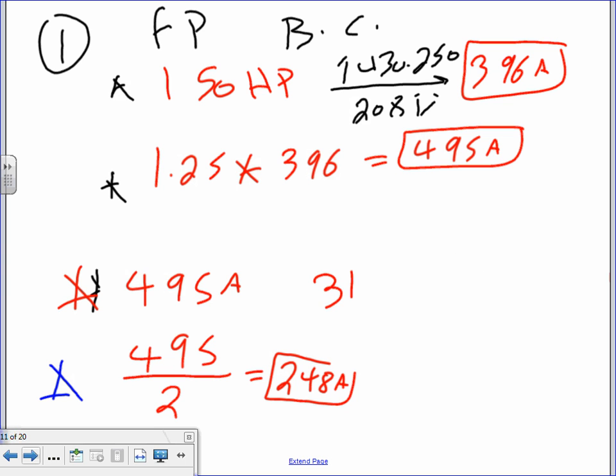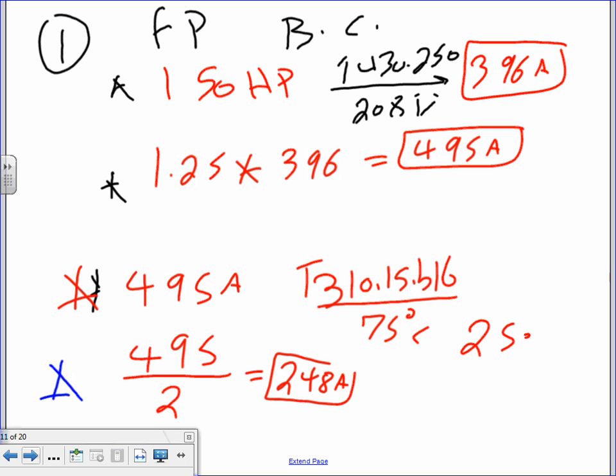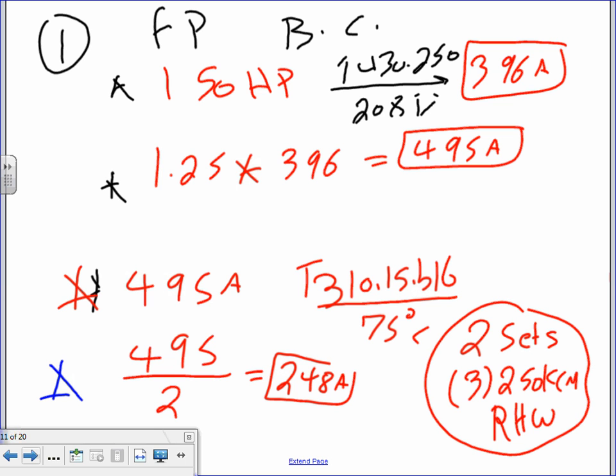So, Table 310.15(B)(16) under the 75-degree column. This is a table. If you guys take it there, after you do that, you're going to end up with 2 sets. Oh, the conductors are 3 conductors of 250 kcmil RHW. Done. See how easy that is? Any comments, guys? Any questions? Straightforward, no gimmicks, except with parallel. Bigger conductor with parallel. Okay. Any comments, questions? Karen, good?